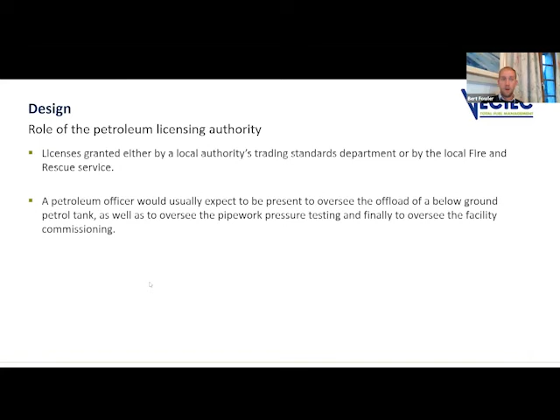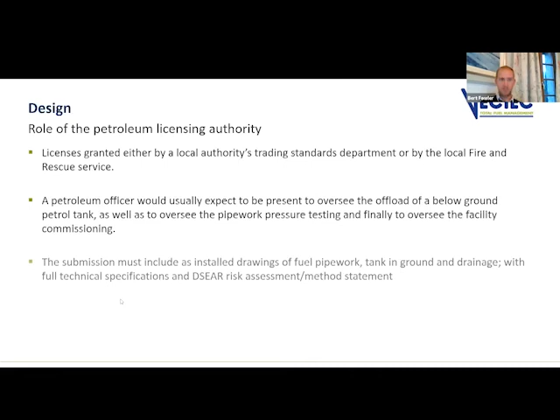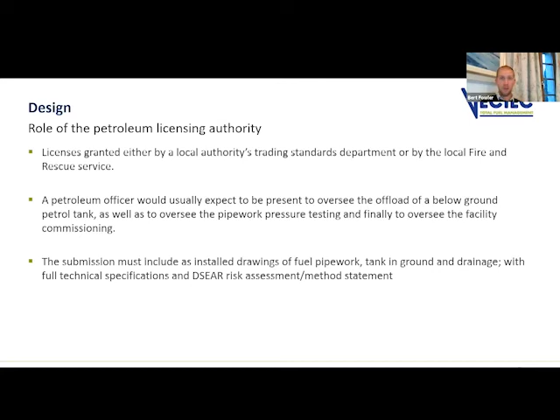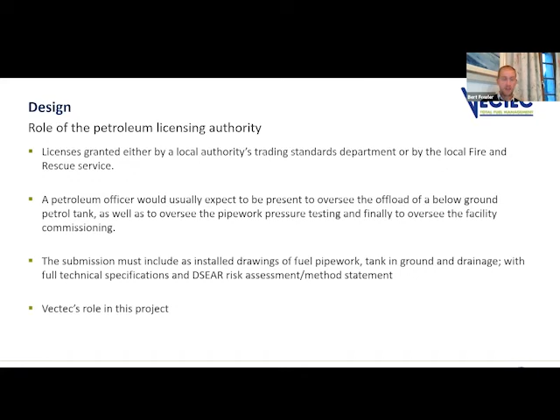Petroleum officers are usually present at the point of delivery of the fuel tank as it goes into the ground, also to witness the pressure testing, and finally to oversee the commissioning process. COVID made that slightly challenging this time, so that was achieved through a lot of photos and documents being emailed across. On top of this, the license submission must include as-built drawings of the pipework in the ground, the drainage plan, the tank, and technical specifications of every bit of equipment relevant to that refueling facility, as well as a full DSEAR safe operation method statement and risk assessment to ensure everybody knows how to use the facility safely and properly.